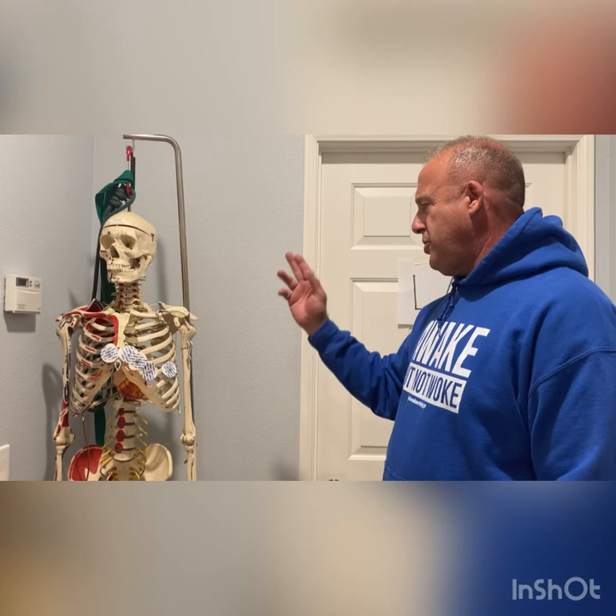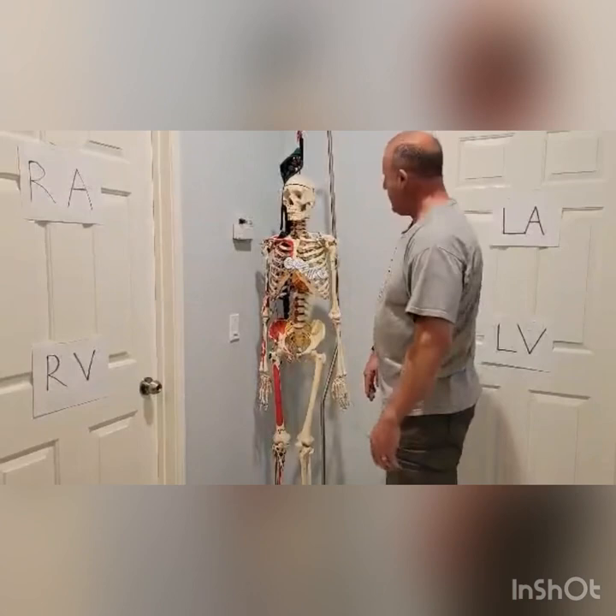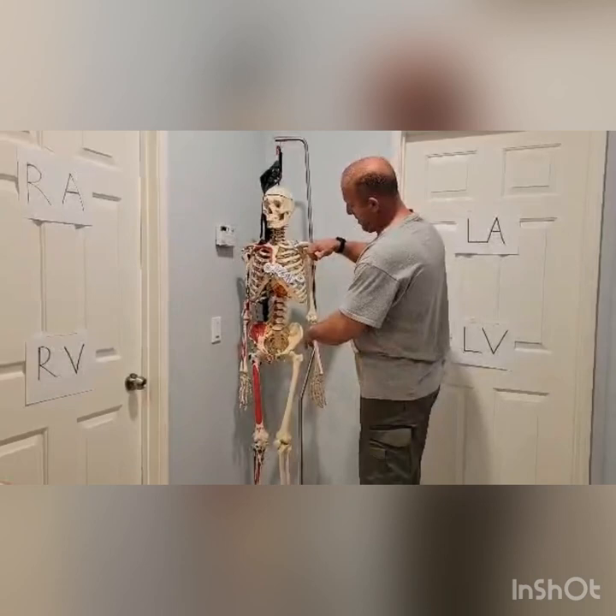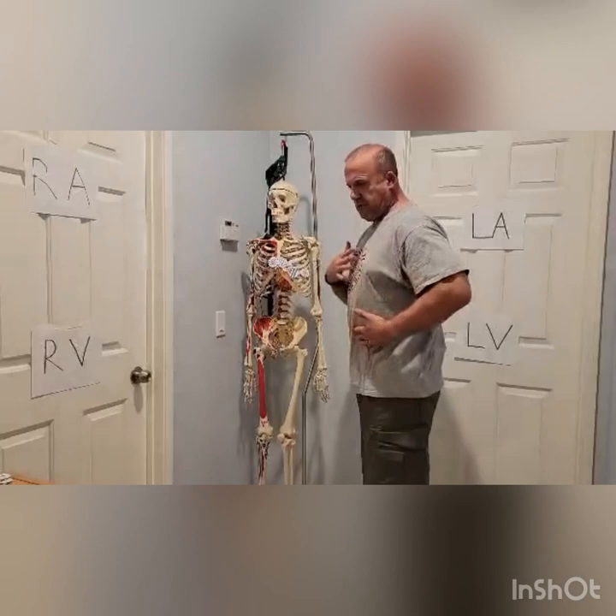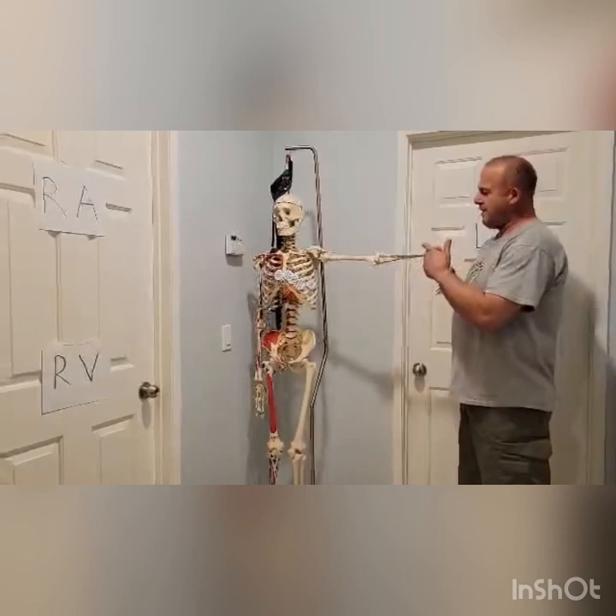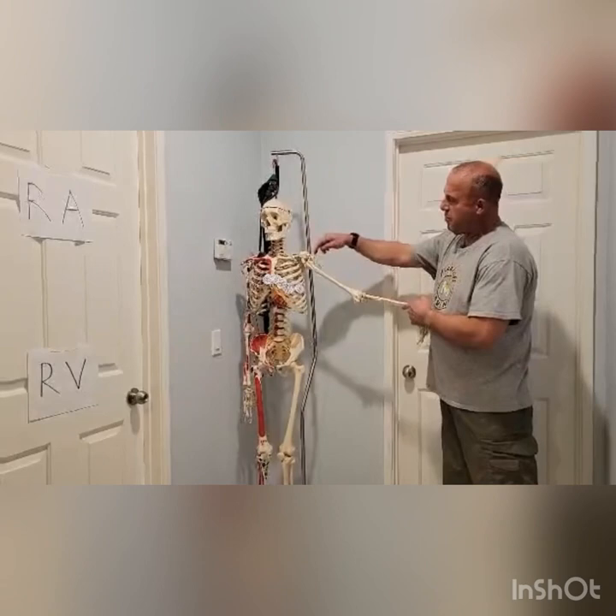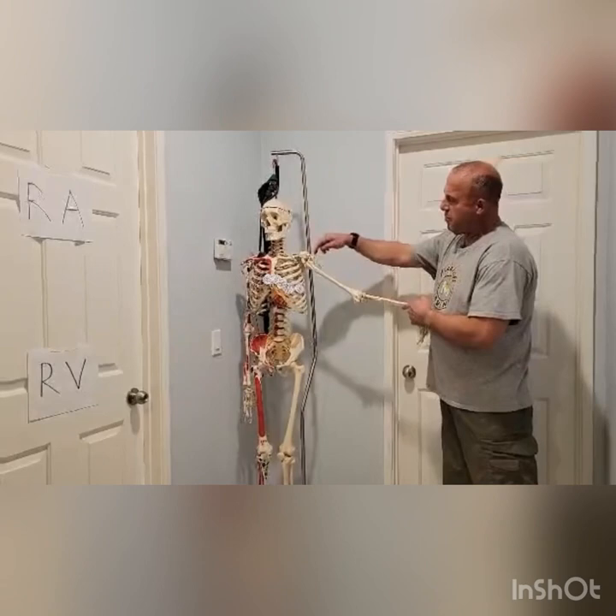For limb lead placement: if you're going at the wrists, go to the ankles; if you go to the elbows, go roughly at the mid-thigh; if you go to the shoulders, go as high up in the hip as you can. If you're placing on the chest wall itself, it's super important to get the electrodes at the far corners of all the moving spots — all our abdomens and chests move. Get as low as you can, like where the belly crease is, and up above the rib cage. This is why you're supposed to have the patient hold their breath while running a 12-lead. When a medic puts electrodes way out at the end of the wrist, you introduce a lot of artifacts — arm movement, shake. The closer you are, the less the wires are in the way, the less artifacts you have, and the bigger and cleaner the signal is without all the hair, fat, and movement between the electrode.